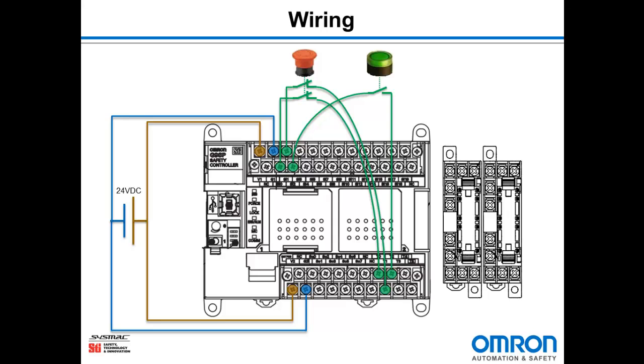The last input we need to wire is the auxiliary contact monitoring to make sure our relays do not weld. That will go from test output 3 to terminal 11 on the first force-guided relay, then terminal 12 over to terminal 11 on the second relay, and terminal 12 on the second relay back to safety input 3. So it makes a loop between the two safety relays.